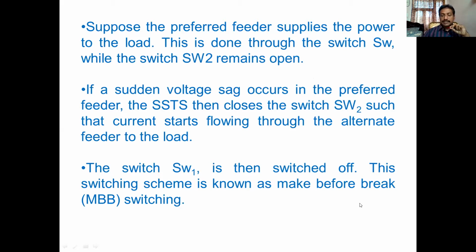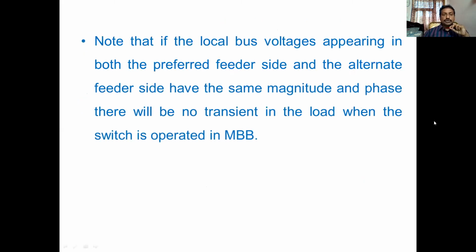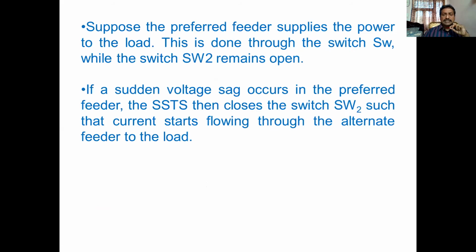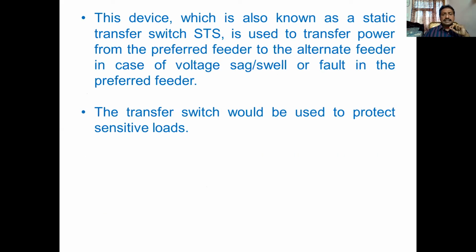So, MBB, make before break. If any fault develops, we don't waste time and want to change over the switch immediately, which is possible with this switch. Note that if the bus voltages on the preferred feeder side and the alternate feeder side have the same magnitude and phase, there will be no transient in the load when the switch is operated in make before break mode. So that is about the solid state transfer switch.